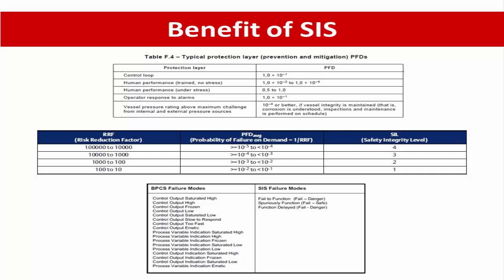The figure below compares failure modes between the BPCS and SIS. BPCS failure modes include several: saturated control output, saturated high, control output high, output frozen, and output low — there are many failure modes for the BPCS. In contrast, the SIS has fewer failure modes: fail-to-function, spurious function, and fail-safe or delayed response. Only three or four failure modes are possible for the SIS.